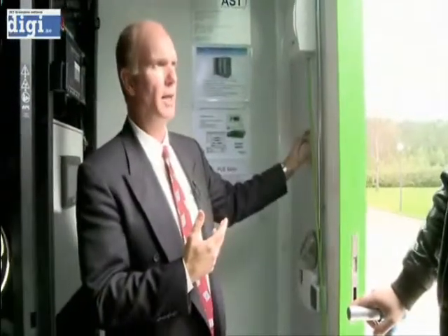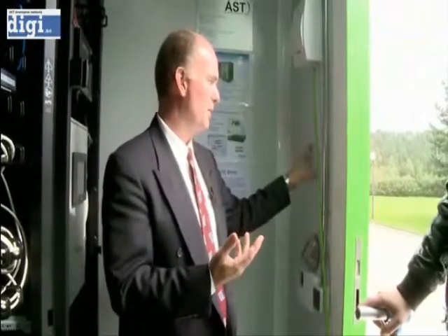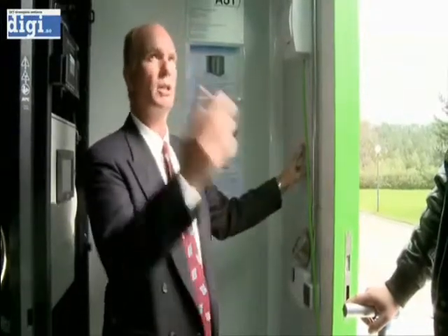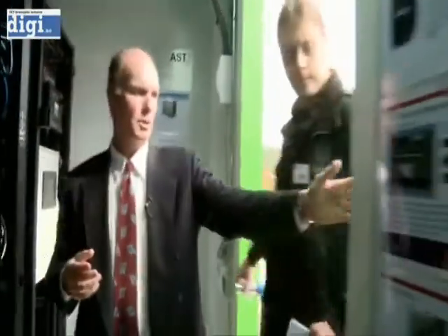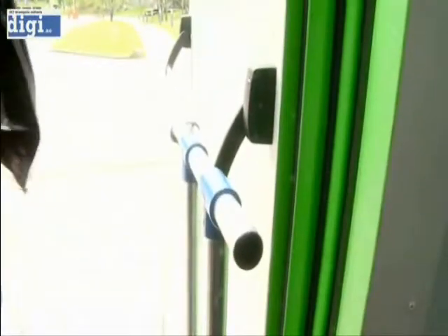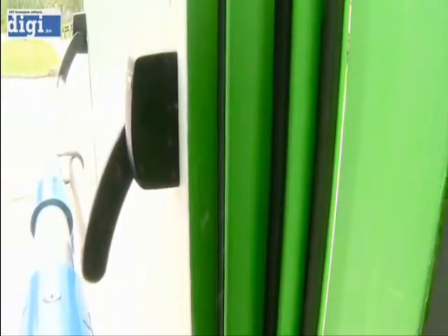It's also fire protective. It offers 120 minutes of passive fire protection, as well as protection from radio frequency interference and electromagnetic interference. So it's a very, very good insulation material, and you see the entire container is sealed with it. In fact, you can see how solid the door is with that insulation material. This is a special door that we put inside the container. We don't use the large end double doors. And you'll notice each door is triple sealed. We have 3 different types of gaskets, so that protects against any water penetration, smoke, fire, humidity. So it's a very tight seal.